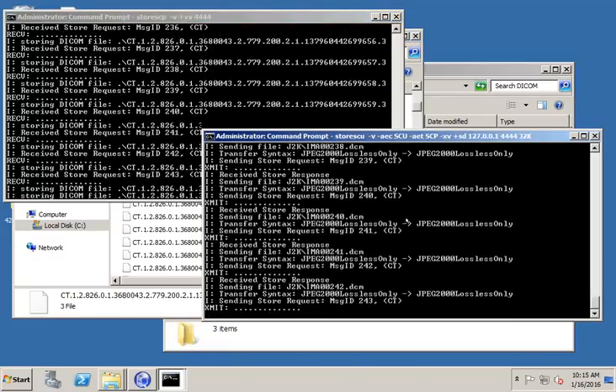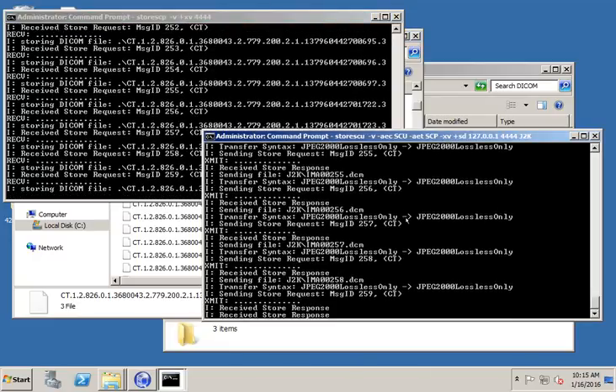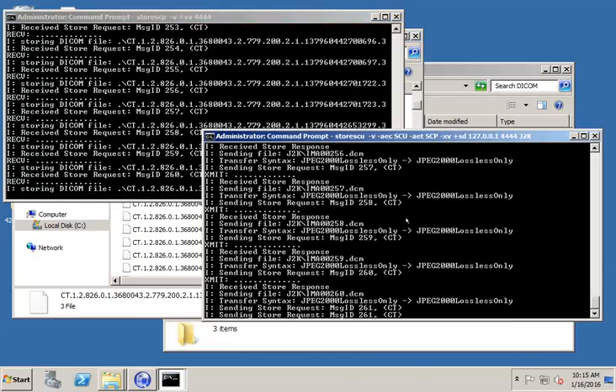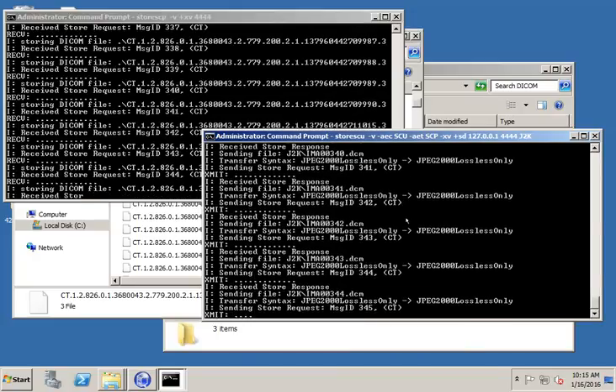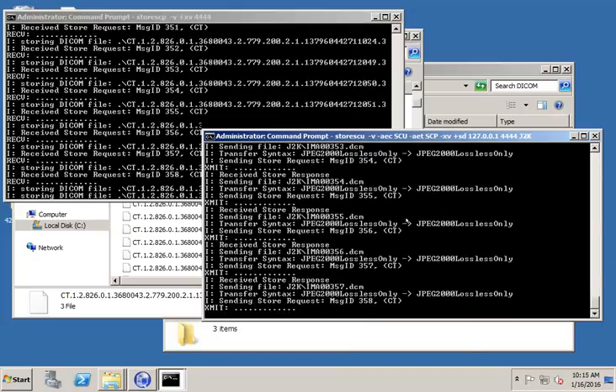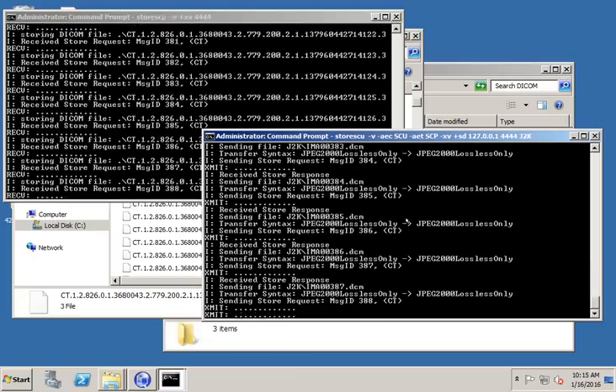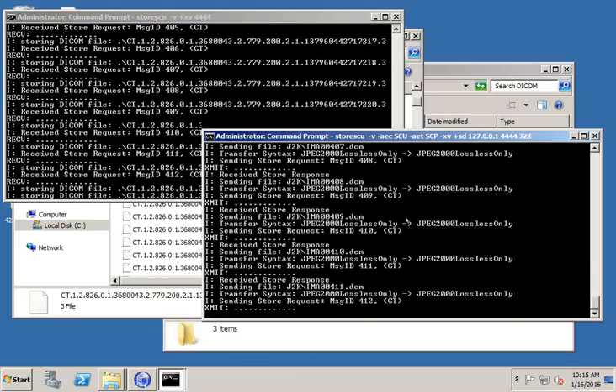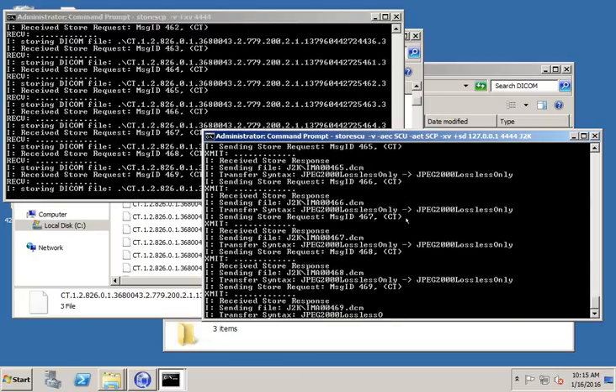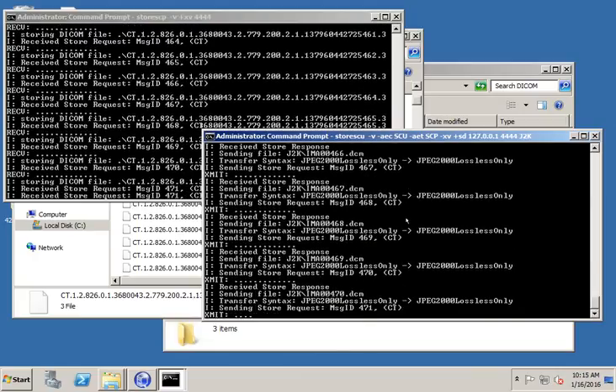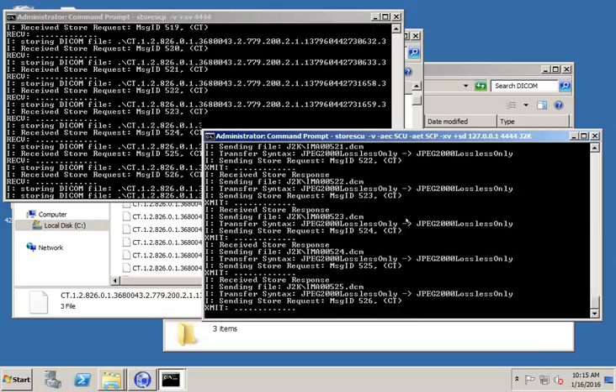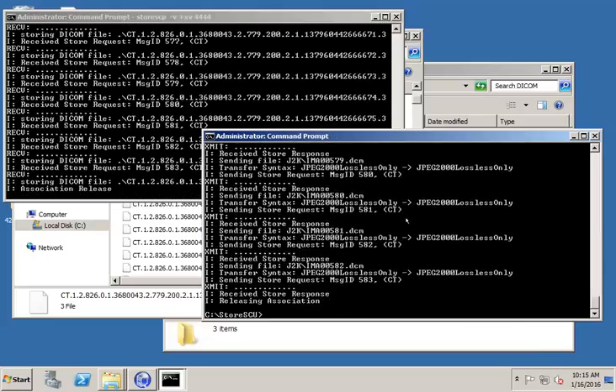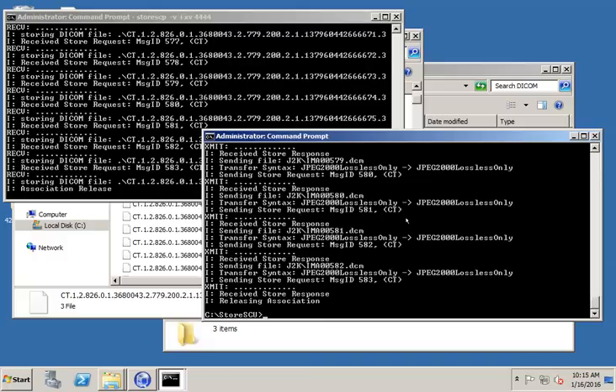So I showed you a number of things. I showed you how to set up storeSCU to send compressed or uncompressed and how to use AE titles. With these basic commands, you should be able to troubleshoot using just about any type of modality, as long as you have some files you can use to send to an SCP. So if you have a PACS, you want to test sending to it as if you're a modality or a node or a view station or whatever, you can do that. And likewise, if you want to test receiving DICOM files from some node on your network without using the PACS, you can run storeSCP to do that to receive the files. StoreSCP is also useful if you're in a pinch. If you need to get some files, maybe for some reason they're not sending to your PACS, but you got to get the files out of the modality, you can use something like storeSCP to do that. I hope this was helpful. Thank you for watching.